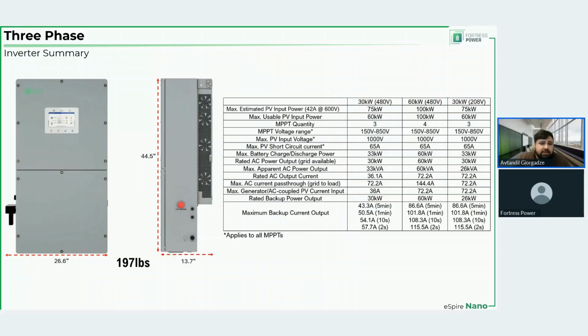Voltage-wise, I'm not even mentioning that because your voltage really is not going to change. It's in series, and the strings connect to each other in parallel. So the voltages will be close, and the module quantity per string really determines the voltage. But when you have 2 strings connected in parallel, the current doubles, right? So pay attention to that when you are designing your system. Although I find it difficult to remember a model type of PV that can exceed around 32.5 amps short circuit current. But again, there are extreme temperatures and there are new non-conventional modules, so to speak. So 65 amps is the limit.